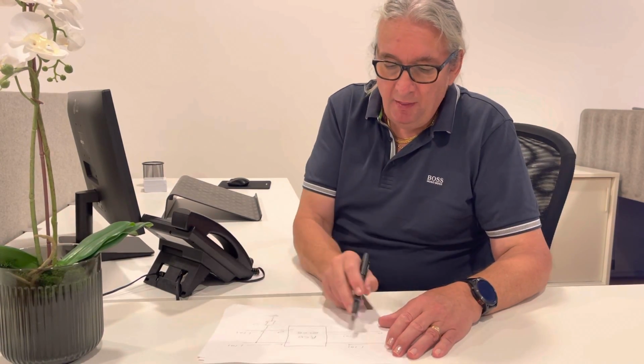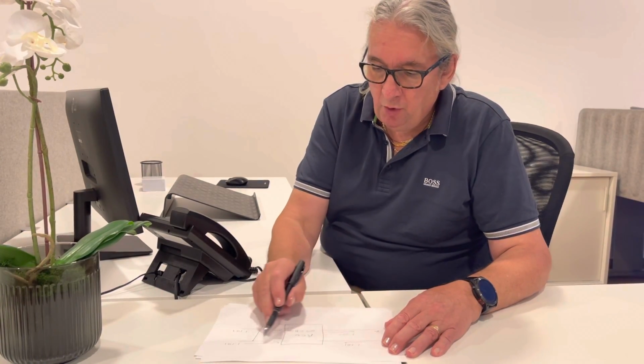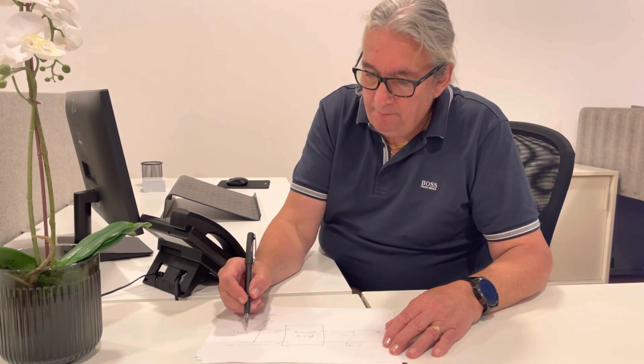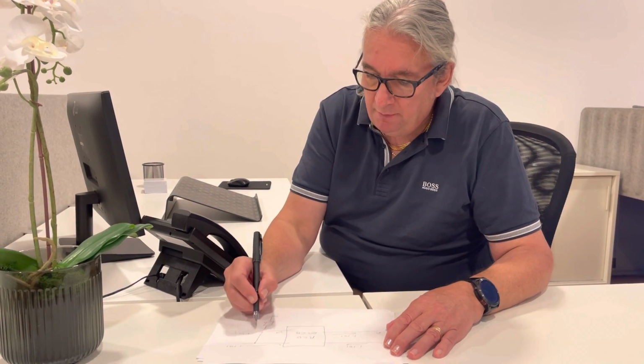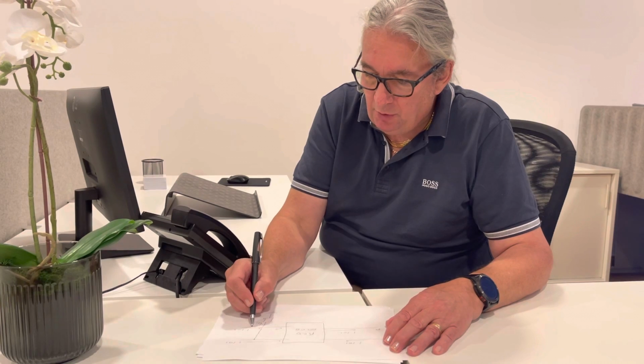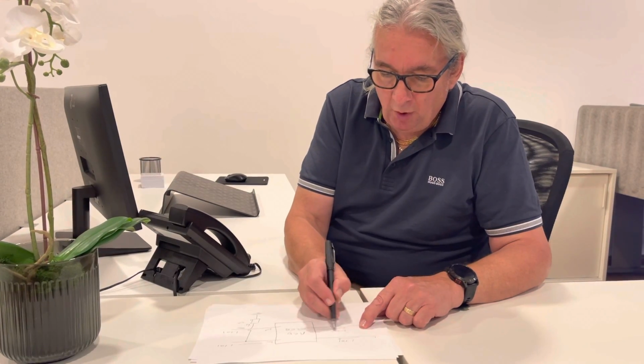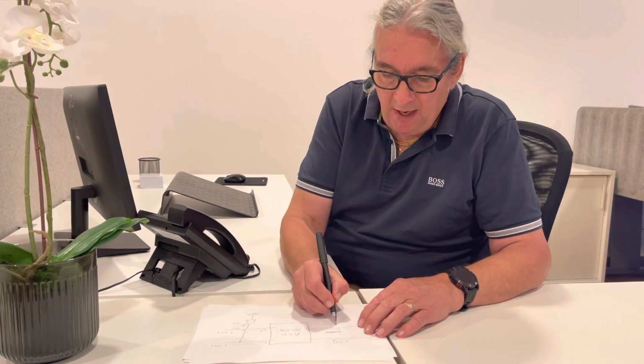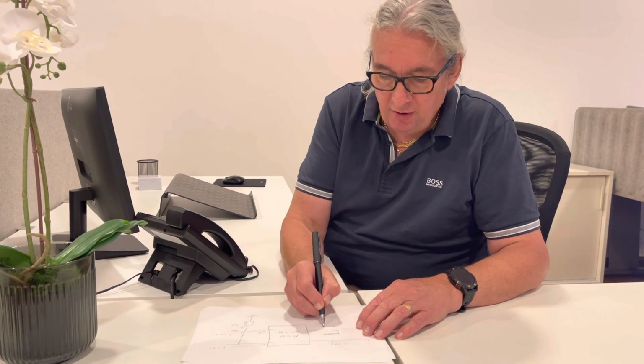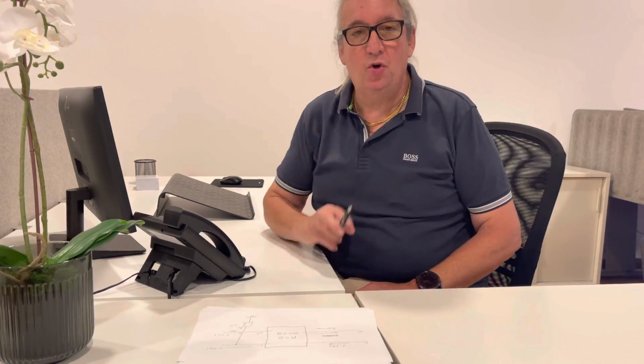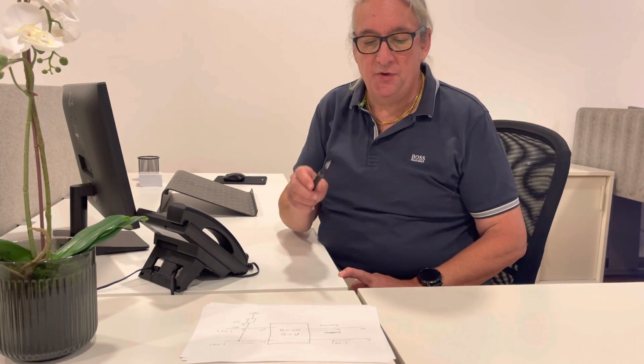and I touch it here. That means the 1.1 will go in, but some of the energy would come down this way and some of it would go that way, and therefore what would come back on the other cable may only be, say, 900 milliamp, okay, 0.9 of an amp. That's an imbalance, and that will cause the RCD to trip. If I was to do the same with the neutral wire, the same thing can happen. It causes an imbalance in the power.